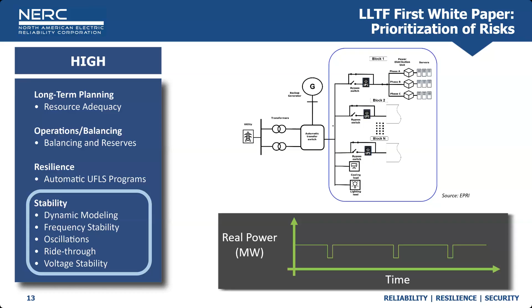This is broken into generalized stability and models. Parts of the level 2 alert identify a need for the load owner or the entity responsible for the large load to supply modeling data so that transmission planners can study their impact. And so you see there an example of the types of load that are within a data center, including the backup generator components. And so we would need models in order to reflect in steady state or transient time domains the impact any loss or change would have on the rest of the bulk power system. And so these models are assessed through frequency stability, oscillations, ride-through, or voltage type stability. And so I'll go on to the next slide, as I think that's a little bit more telling as to how these will play out.